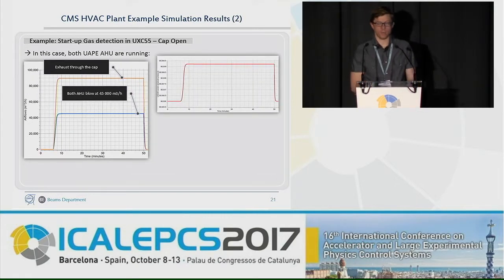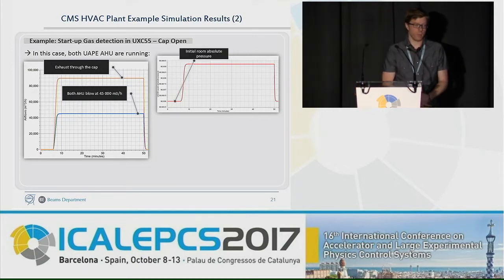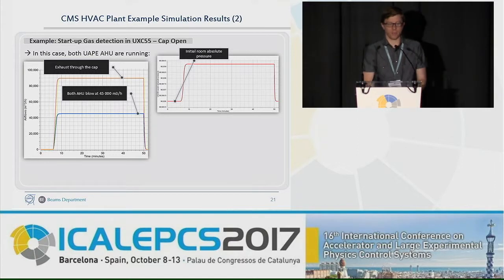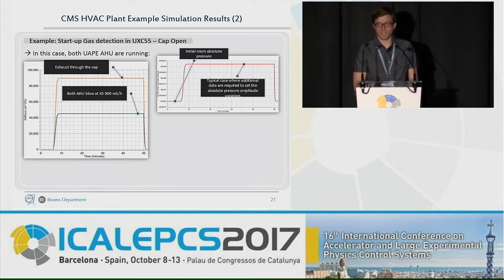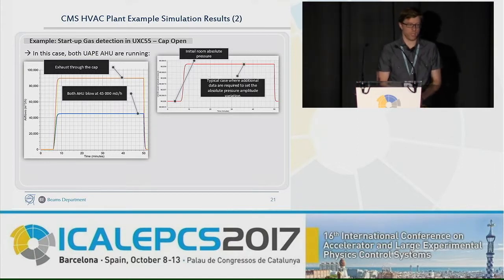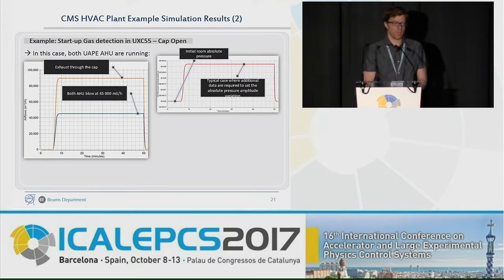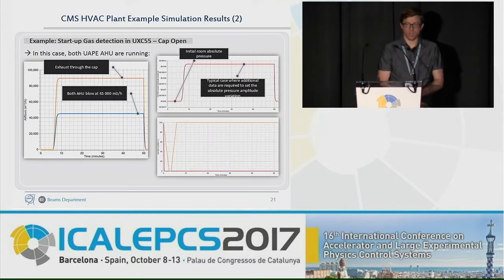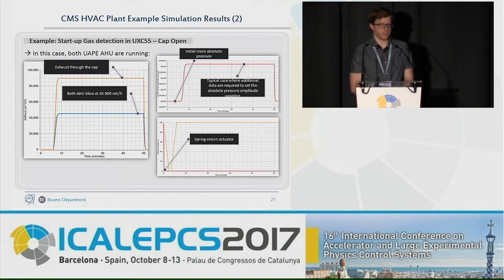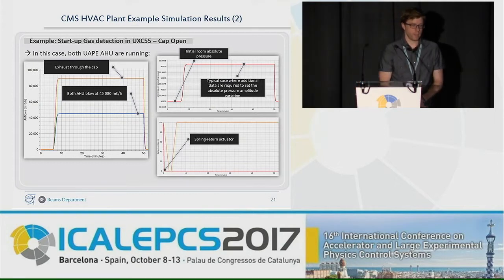And since we're interested in maintaining an under-pressure in the Cavern, we plot the Cavern pressure increase. Again, we would need additional data to validate the absolute amplitude, and we can plot modulating damper positions over the transient.